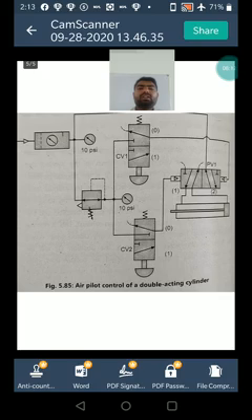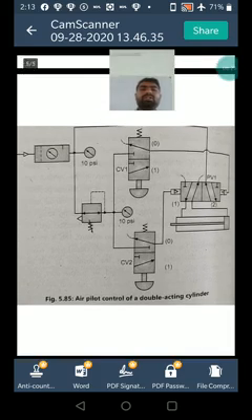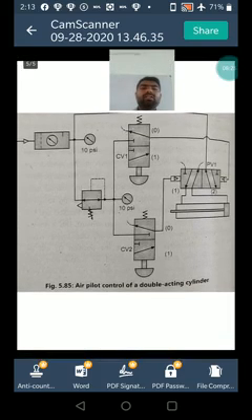The rod end air exhausts to the atmosphere. This position is retained till the pilot signal from CV2 is obtained. Now second step: pressing CV2 gives it position 1 and supplies a pilot signal to port 1 of PV1. In this position, the cylinder retracts. Thus high pressure air to the cylinder is controlled by low pressure push button valves from a place away from the cylinder.